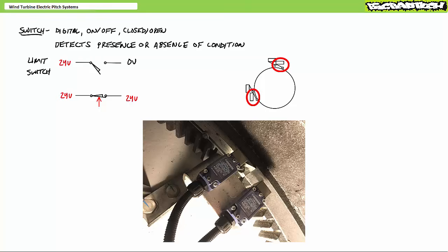The second pair of limit switches are in effect backups to the first set should this initial set fail to function. Limit switches, after all, are electromechanical devices, and actuator arms and the tags they are intended to interact with can and do break off, get twisted at weird angles, get stuck, or covered in goo. If the blade pitches past the first set without detection and strikes a member of the second set guarding the border of no man's land, the system can signal a pitch error or a fault and take appropriate action to correct it.